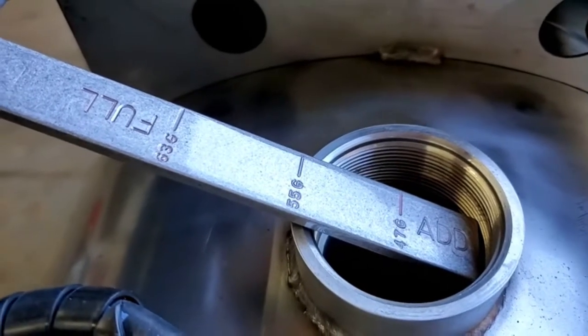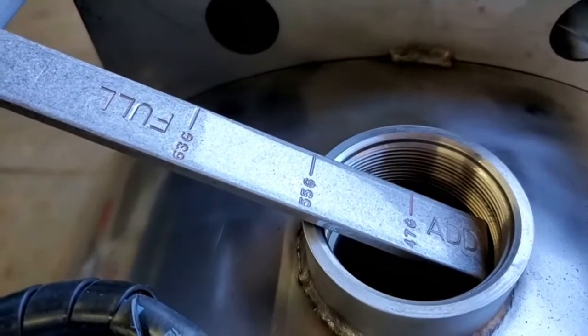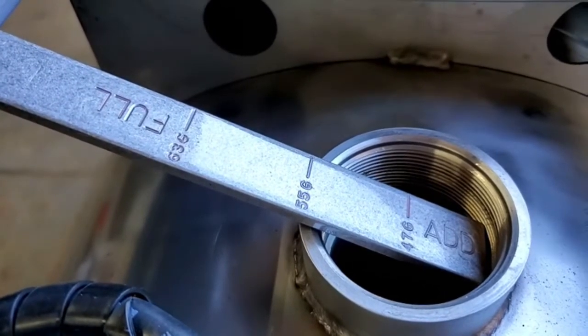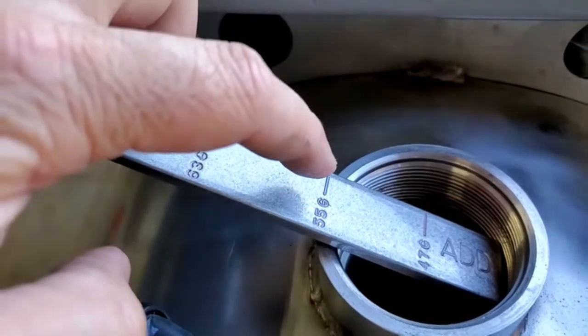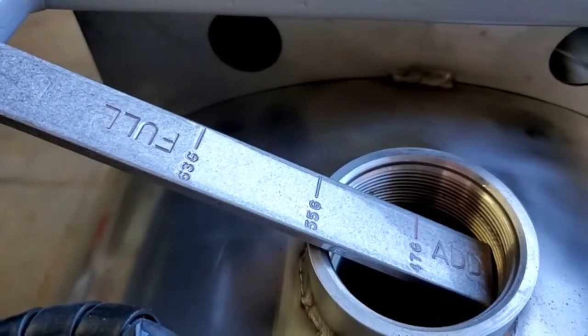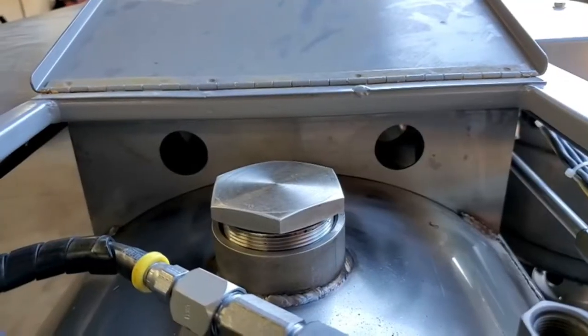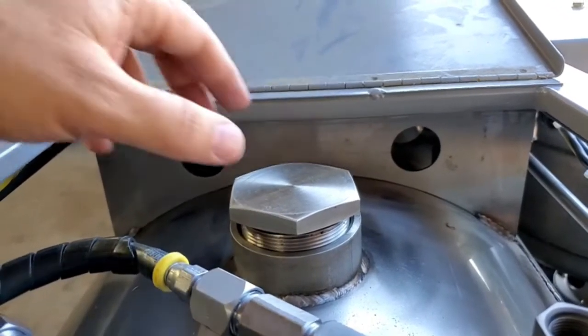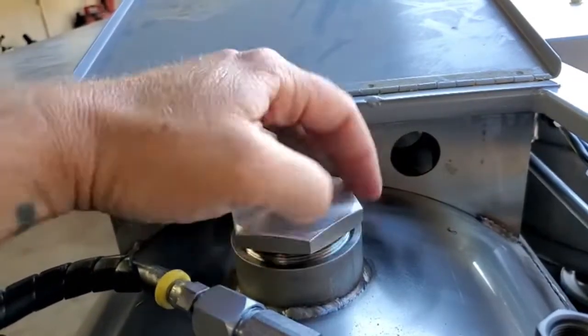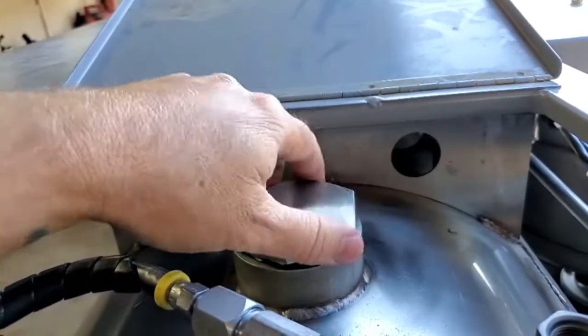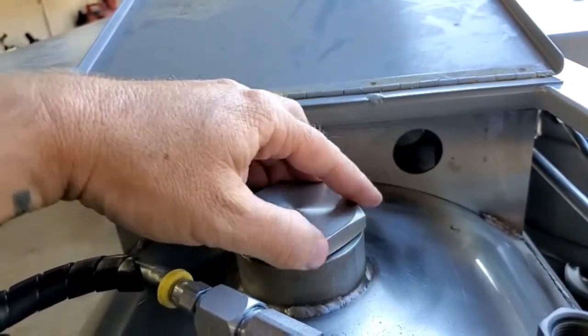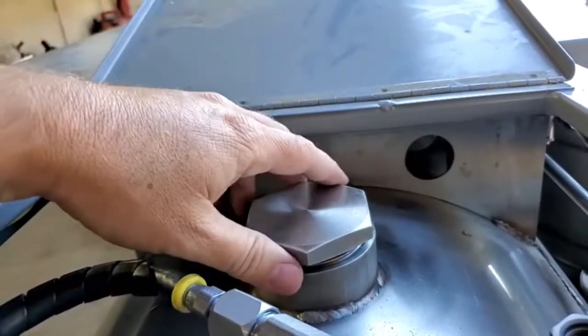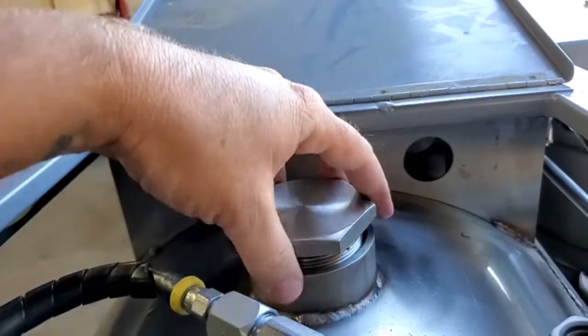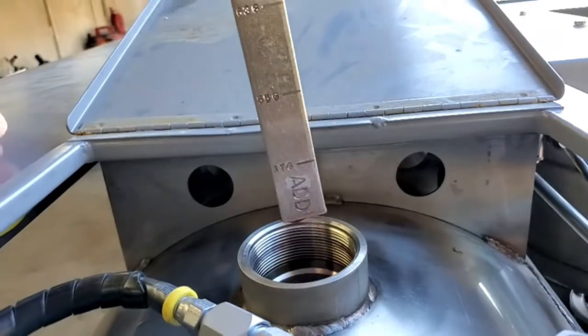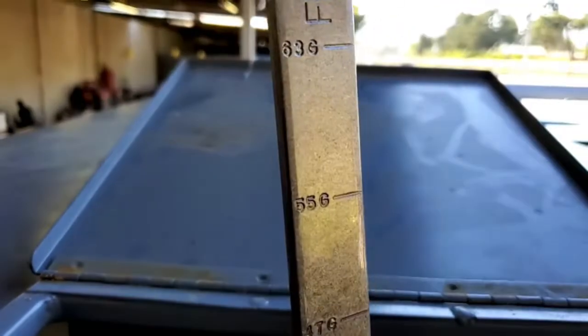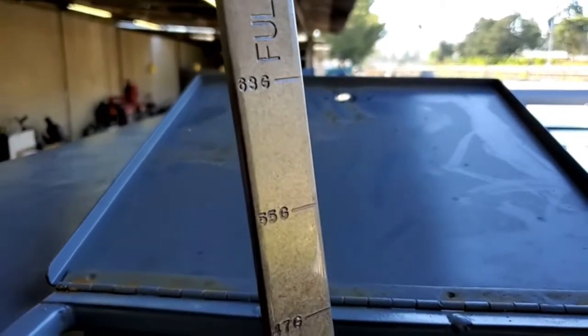You can see here on the dipstick you've got 3 levels to work with: 47 gallons, 55 gallons, and 63 gallons. My suggestion, go ahead and get it to 55 gallons. Now that you've serviced your reservoir, go ahead and insert the dipstick and screw it all the way down. Once it stops, go ahead and unscrew it, pull it out and double check your fluid level. We're at approximately 56 gallons.